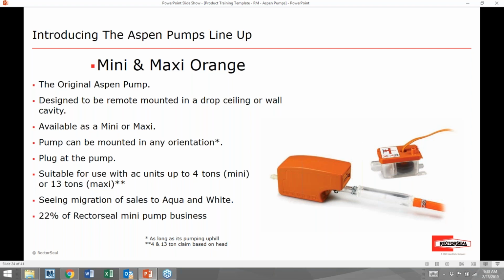However, I alluded to it much earlier in the presentation, this is the first pump we've talked about that is available in a Maxi. So as the name would indicate, the pump is larger, but it also is a little bit more noisy. Both the Mini and the Maxi Orange have a power plug that's at the pump as opposed to pigtails, but this is still okay. This pump is fully potted, and at the terminal inside the pump, there's a sealing plate. So even if it was to get splashed with water or a little bit of debris was in there, it's not going to go far and can be easily cleaned out.